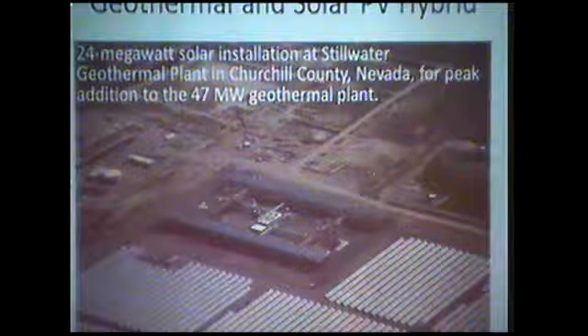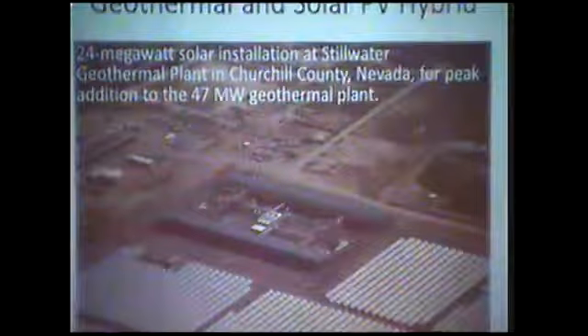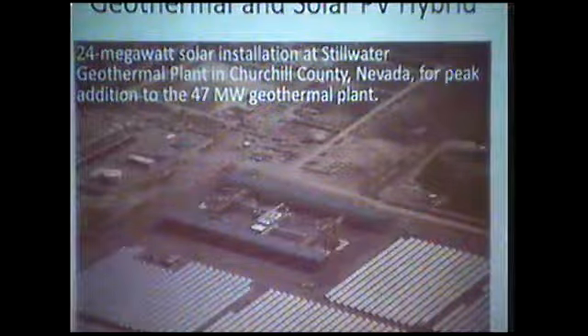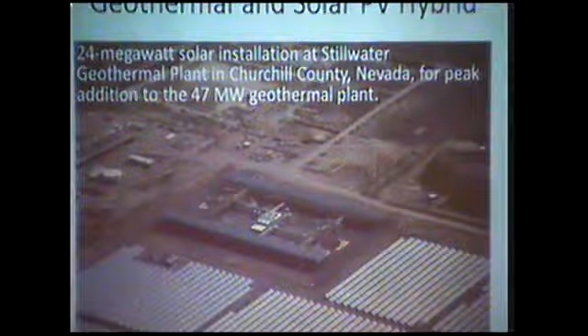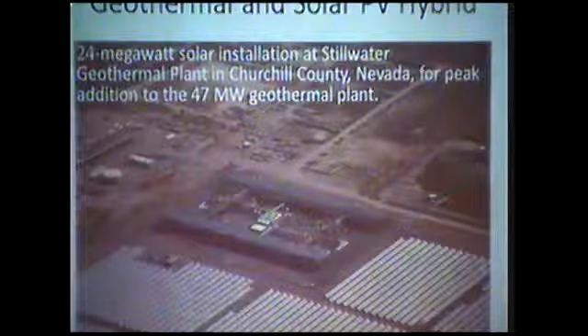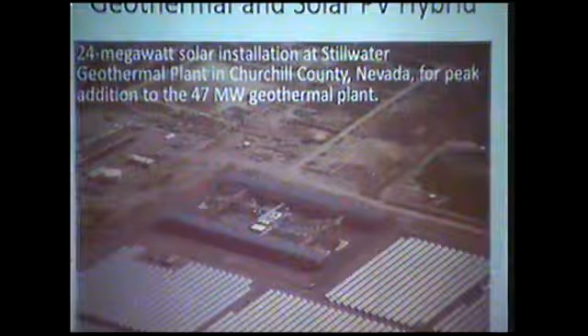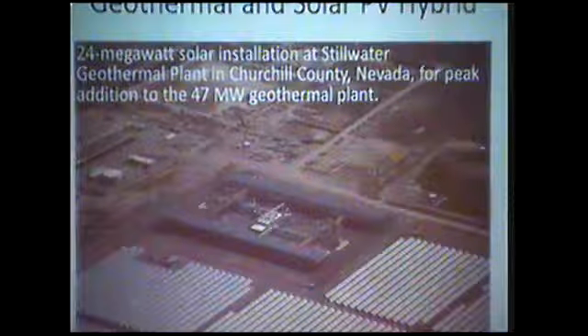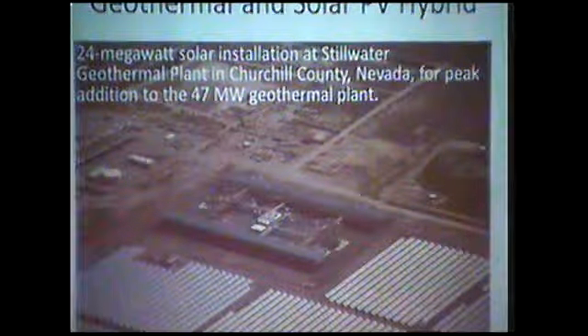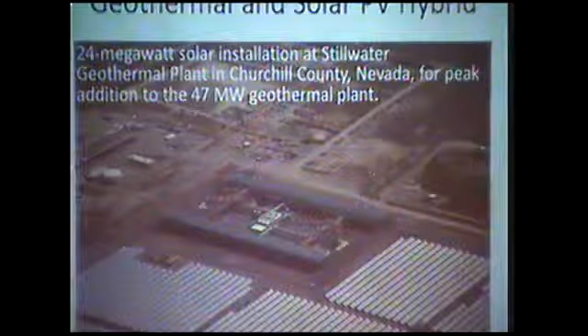This has a specific advantage because binary power plants tend to be inefficient when the atmospheric temperature is high. They're obliged to use air-cooled condensers rather than water or wet cooling towers. Therefore, in the afternoon at 3 o'clock, when the temperature is hottest, the power plant has its lowest output because that's where efficiency is least. That's not ideal, because 3 o'clock in the afternoon, especially in Nevada, is when it gets hot, everybody turns on their air conditioning, and that's when actual electricity demand is greatest. That corresponds to the maximum output from the photovoltaic panels, and therefore the photovoltaics fill the gap that the reduction in capacity from the exchangers represents.